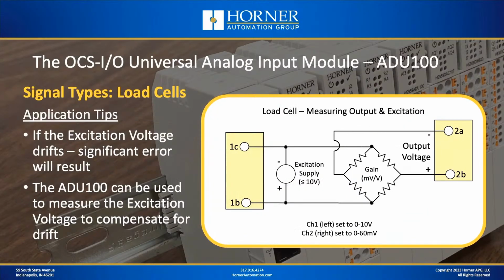Now, one thing that can happen with load cells is that it is possible that your excitation voltage, that's the input to the load cell, could drift. Generally with load cells, you're going to be selecting an excitation supply with really good specifications so that you get a good constant voltage that doesn't drift. But if you have concern about voltage drift of your excitation, you could connect your excitation supply to another channel of the ADU100 and measure that voltage, as long as that excitation voltage is 10 volts or lower. So that's one way that you can use the ADU100 to not only measure the output of your load cell, but also verify the excitation voltage. And if it does drift, you can compensate your reported load cell readings appropriately.